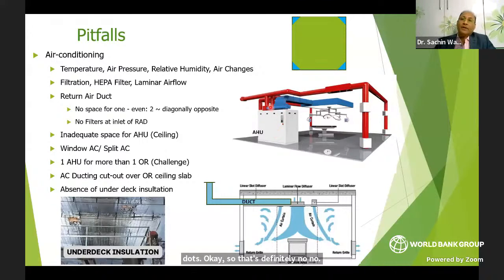At times, people are not able to get all four corners for return air ducts. In that scenario, it's better to have two return air ducts, diagonally opposite, so we can maintain laminar airflow as much as possible. Laminar airflow, as they say, lamina is the layer.